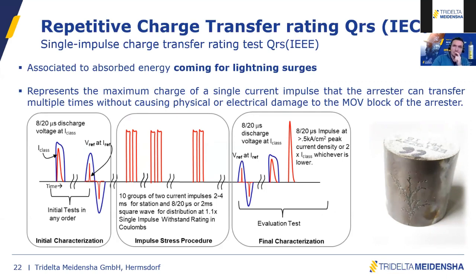So we take 10 blocks. This is what the IEC standards define. We take 10 blocks, and for each block, we have to inject 20 impulses. This diagram shows the typical process that you do on each block. Before each test, you do an initial measurement or initial characterization of the block with residual voltage and reference voltage, which are actually these two ratings done in the routine test of the arrester. Then you do the injection of the lightning impulses, or typical lightning impulses. And once you have applied the required stress, you do a final characterization, which is actually a pass criterion, where you want to make sure that you don't exceed the initial measurement.